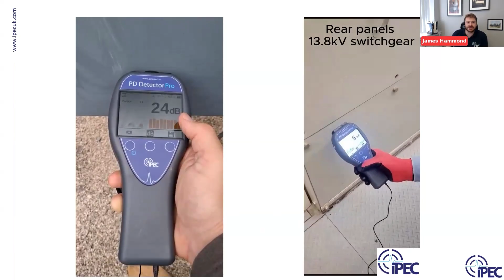And then something like an acoustic emission test, you can see this engineer here testing on the rear panels of 13.8 kV AIS. And again, you can see those patterns building up 180 degrees apart.